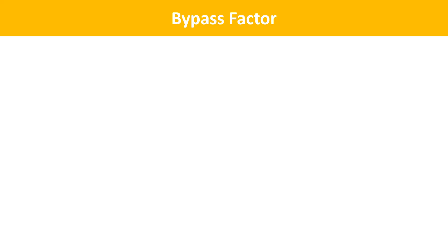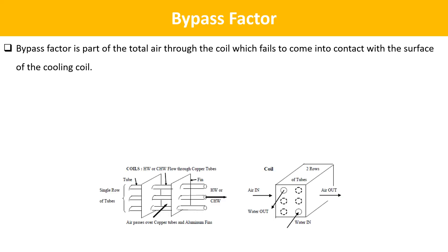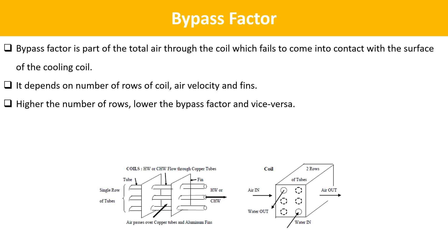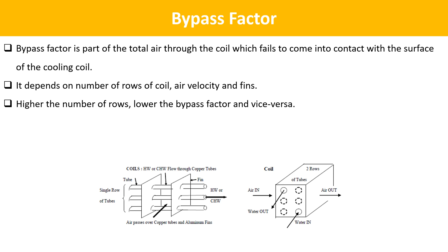The next term is Bypass Factor. Bypass factor is the part of the total air through the coil which fails to come into contact with the surface of the cooling coil. It depends on the number of rows of coil, air velocity, and fins. Higher the number of rows, lower the bypass factor, and vice versa. Higher velocity means a higher bypass factor. The velocity should not be too high, otherwise a large amount of air will get past the coil without sufficient heat transfer due to short contact time.